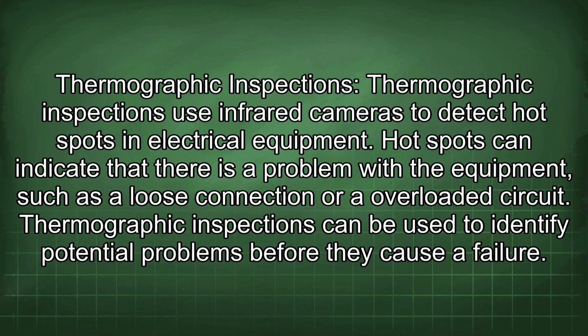Thermographic inspections. Thermographic inspections use infrared cameras to detect hotspots in electrical equipment. Hotspots can indicate that there is a problem with the equipment, such as a loose connection or overloaded circuit. Thermographic inspections can be used to identify potential problems before they cause a failure.